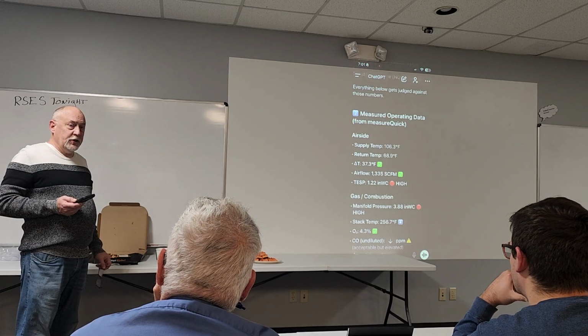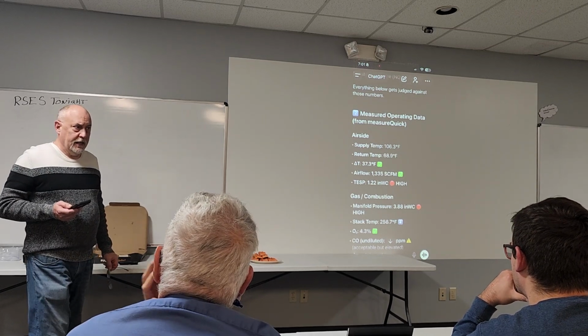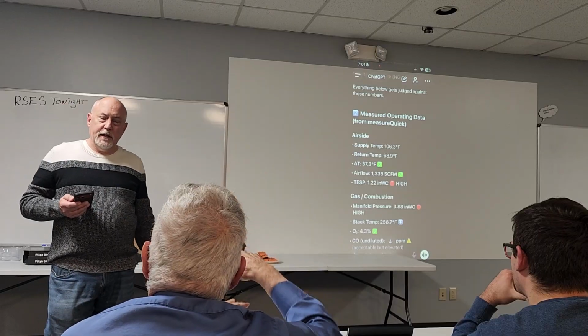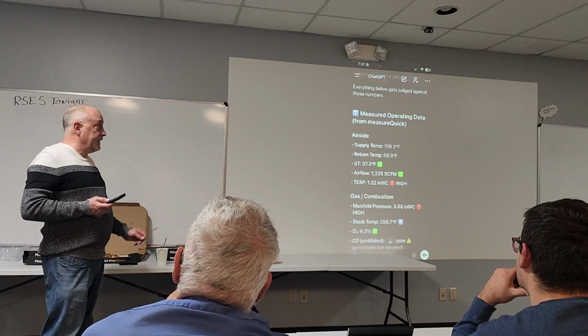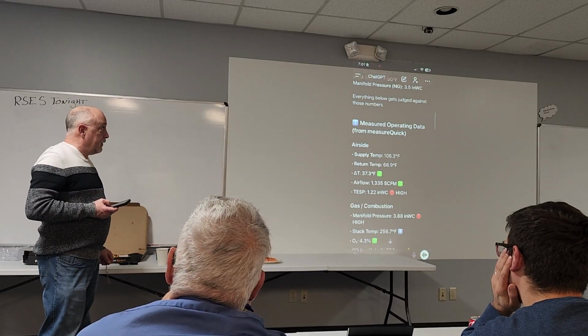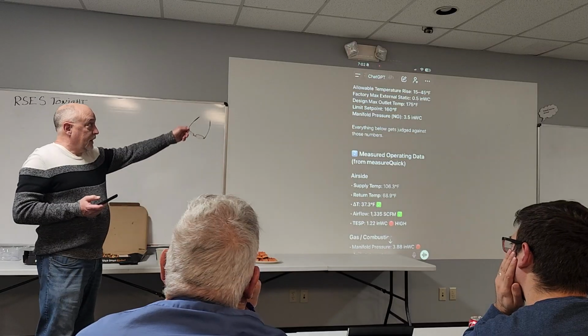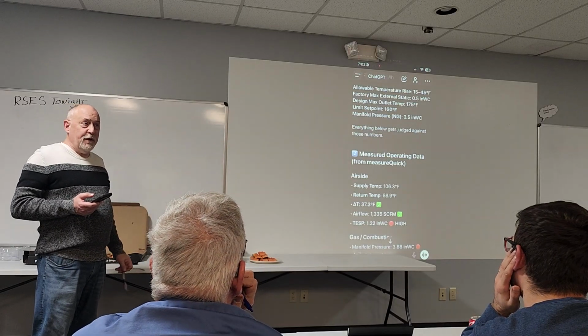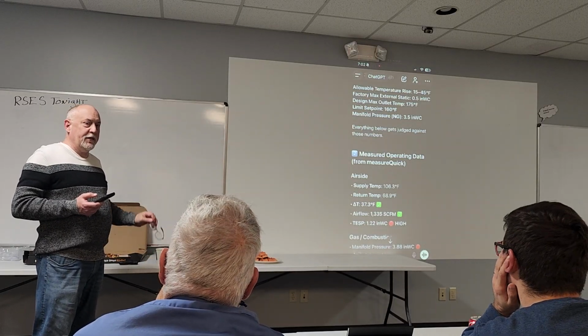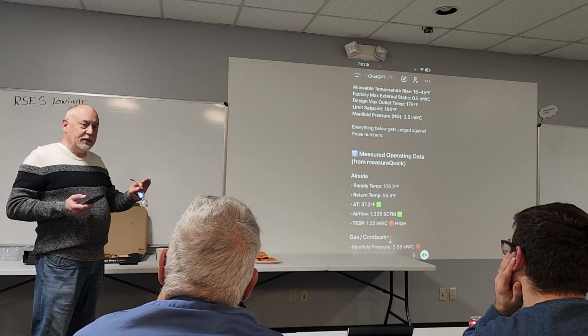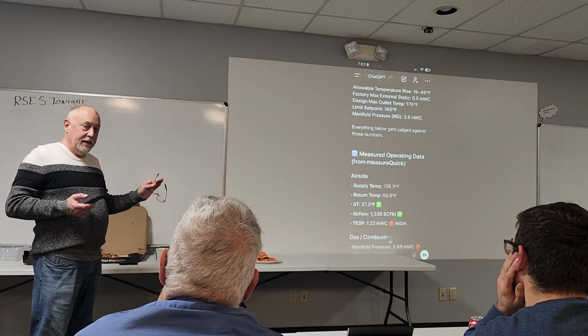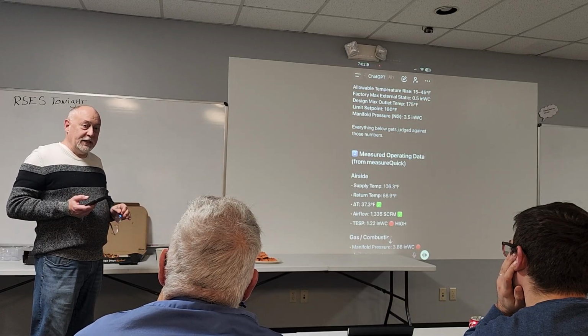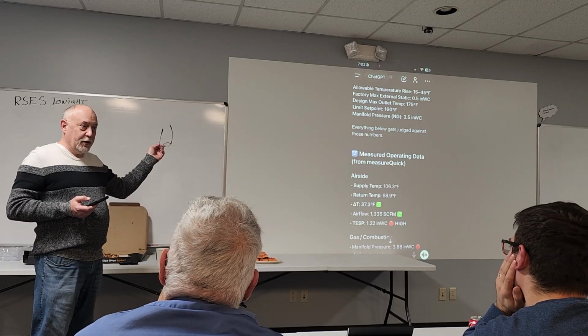What are the manufacturers doing on these furnaces to get the efficiency up? I'm trying to get a lower delta T. This thing's got a delta T that's within spec, but it's at the high range. At 15 degrees, do the math in your head real quick: 60,000 divided by 15 is 4,000 CFM at 15 degrees.